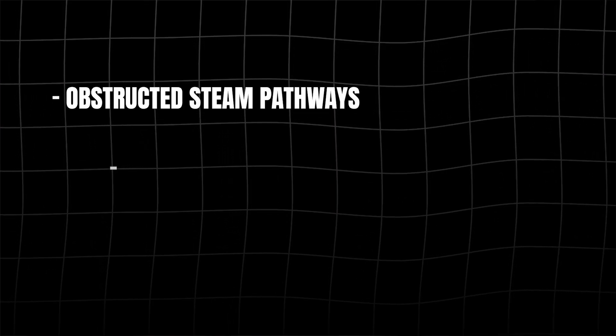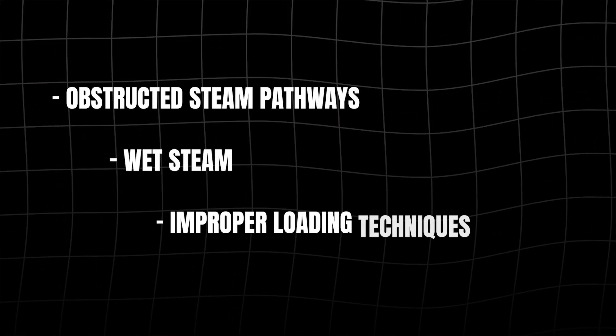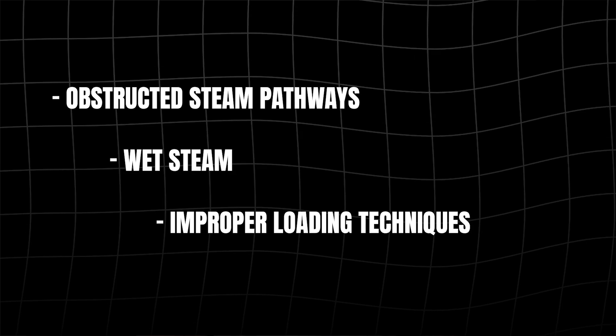Now, if the test fails, it is time to investigate. A few initial things to check for include obstructed steam pathways, wet steam, or even improper loading techniques.